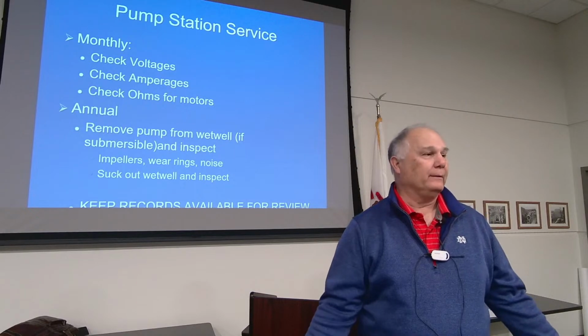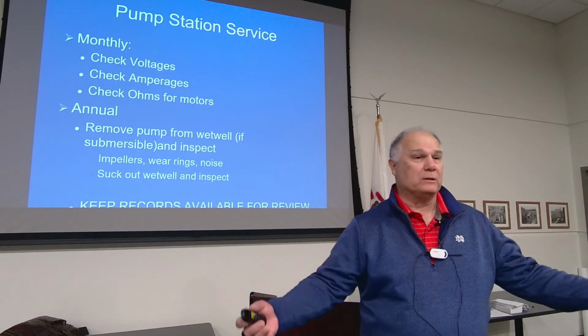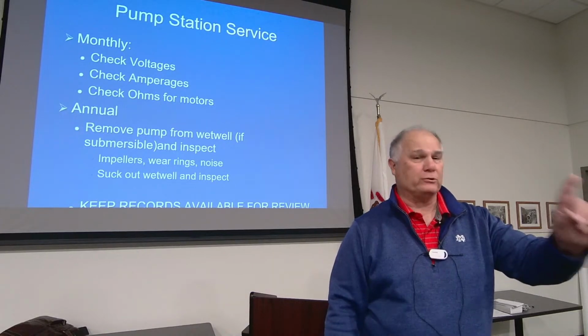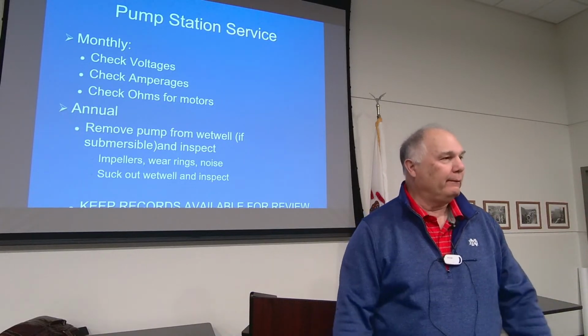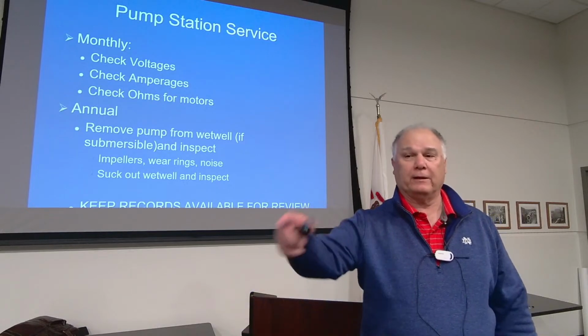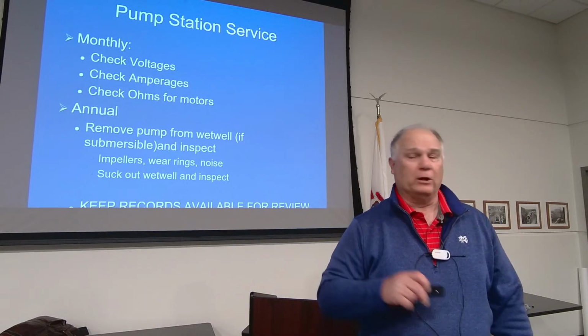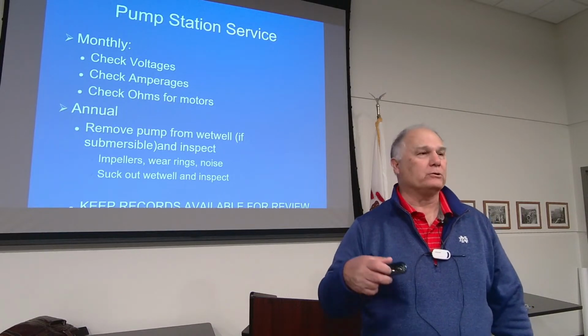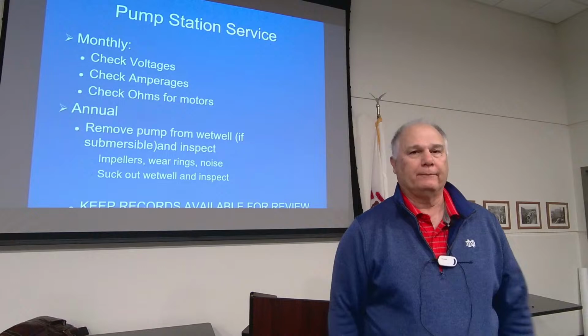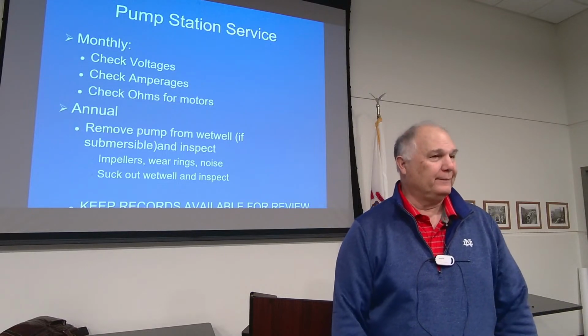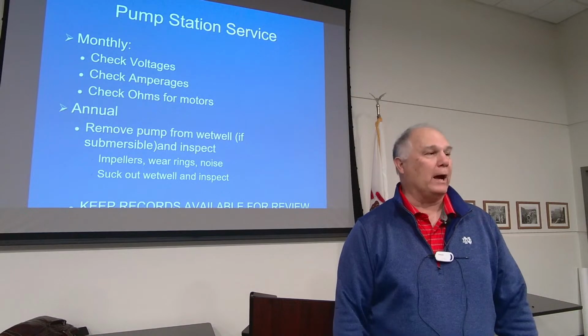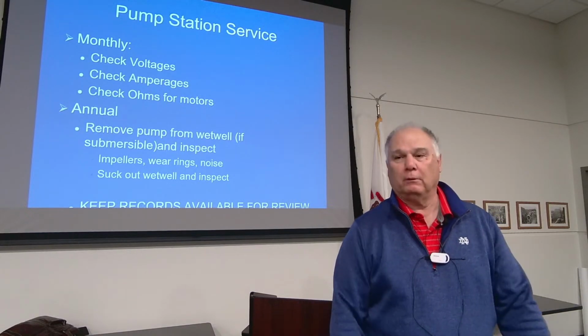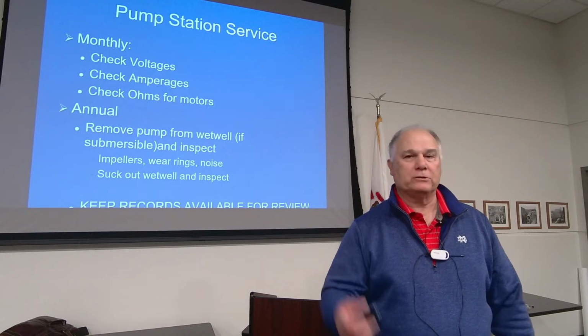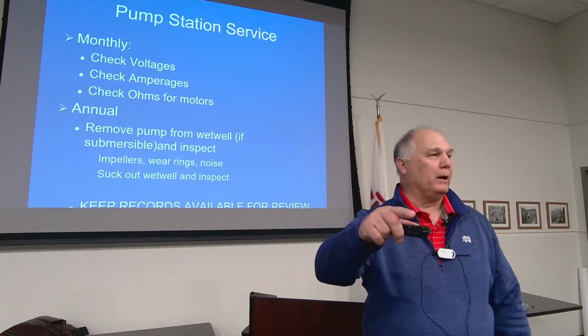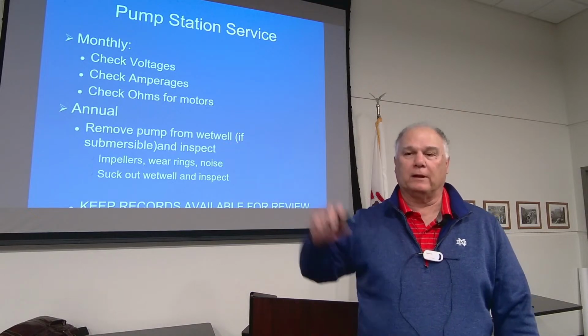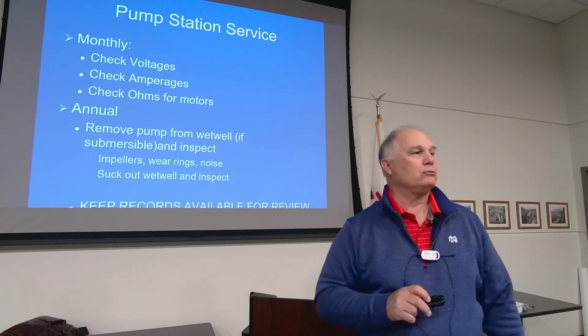So they called me up and said, hey, what's the deal? I asked them one simple question: what's the pressure at the pump? We don't know. Well, if you had told me that, you would have saved yourself digging up all the force main. So they go back and say, well, your pressure is 80 feet, or 37 PSI. Your wear rings are shot. The pump's 15 years old. How do I know? Because when you shut the valve and deadhead the pump, I know the pump is going to go all the way to the left side of the curve, 0 GPM at TDH.